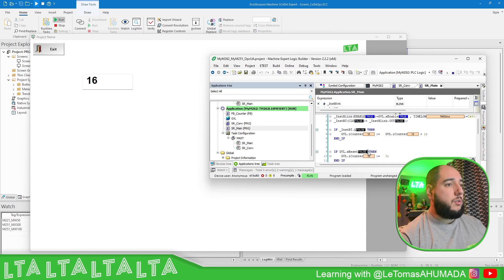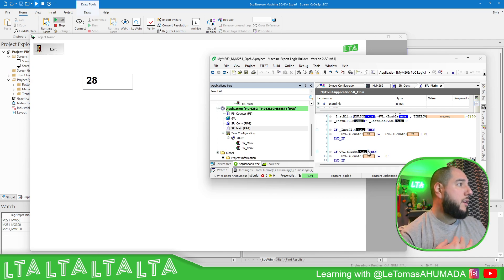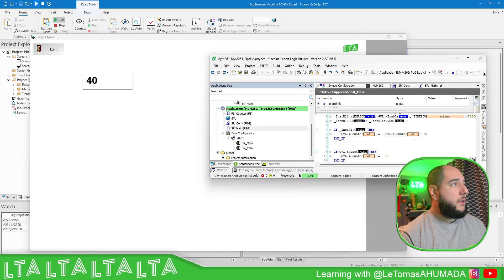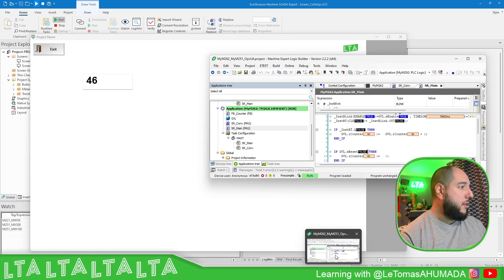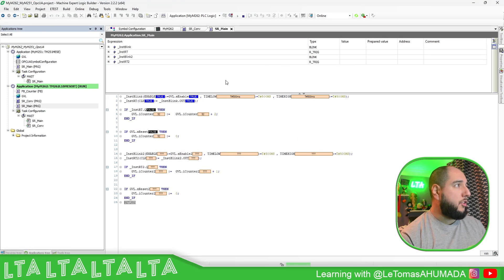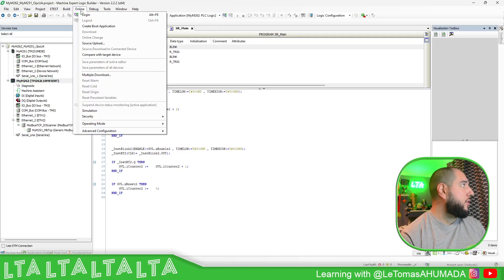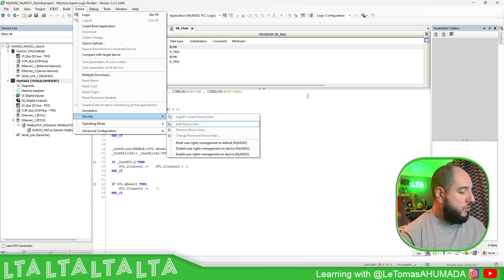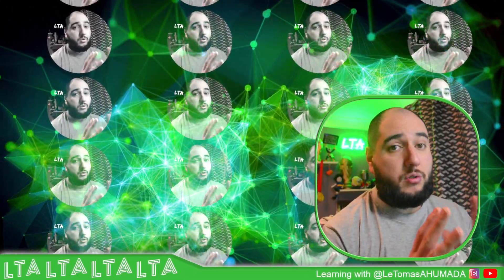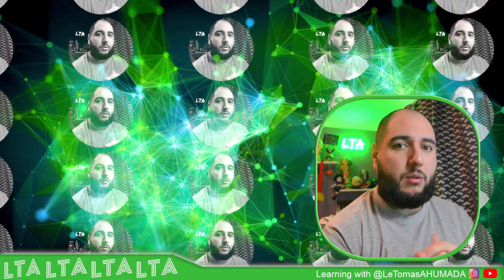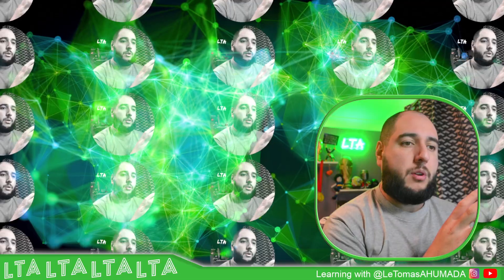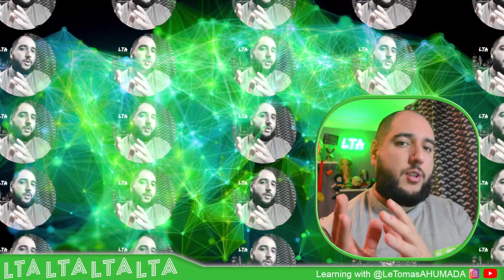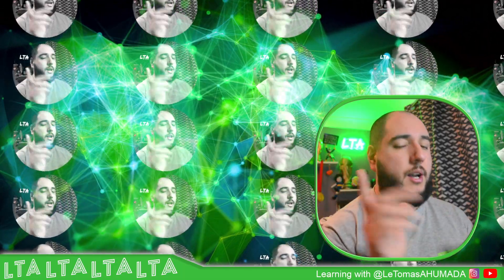There are a few things we need to check: the security, because there is no space on the CODESYS side to put the security. Basically, that's it and it will work. On Machine Expert, if you don't want to go in this direction, just go to Online Security and Enable it once again. And that's it — this is how we can use the communication drivers for easy integration of tags via CODESYS between Machine Expert using the M262 and the EcoStruxure Machine SCADA Expert. Thank you very much for watching this video and I'll see you in the next one.